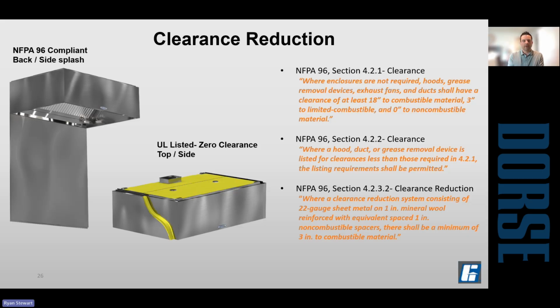So this is just another example of that, and what the code says about it. Basically, all surfaces within 18 inches of the hood need to be non-combustible, or they need to be protected. Another way that you can accomplish this is with an insulated pad. That would consist of a 1-inch mineral wool insulation covered with a stainless steel cleanable surface, and you would install that the length of the hood and 18 inches beyond. I've seen that put on ceilings and those types of things. Ideally, you do what you can to have all materials within 18 inches of the hood be non-combustible.